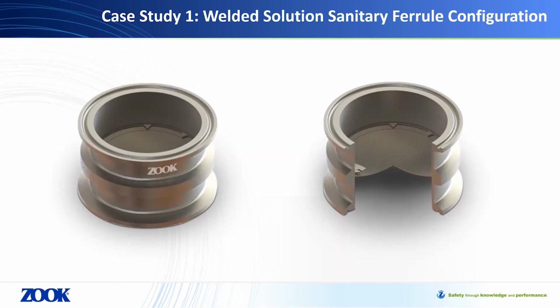For some background on the application, a customer was experiencing a challenge in their existing installation. The installation was challenged with leakage downstream. This challenge can arise at times when a conventional rupture disc is used in series with a valve. You may or may not be familiar with the fact that it is common for various code bodies to require intermittent inspection of a relief valve.